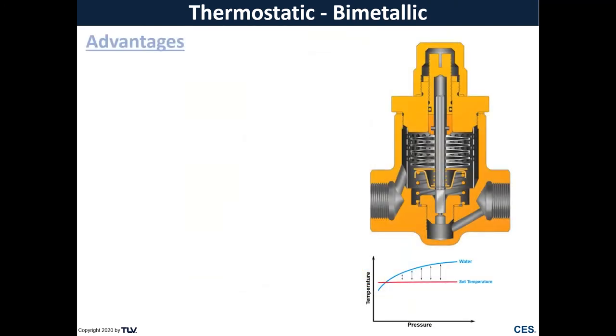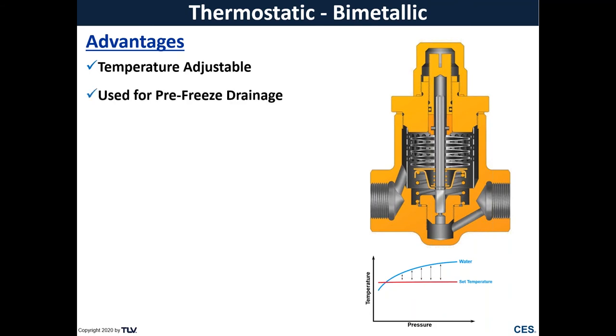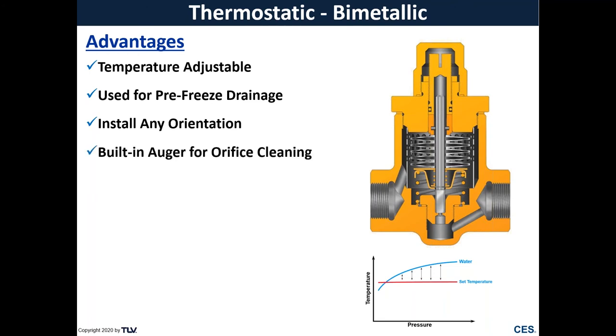Some advantages to this trap type: you're able to adjust that set temperature to better match your application. You can use this as a pre-freeze drainage, so you set that temperature very low and that'll open up to relieve any condensate in your equipment before it freezes. In addition, this can be installed in any orientation since it's really operating off of the temperature change. There's a built-in auger device for cleaning, and I'll cover that in this next slide.